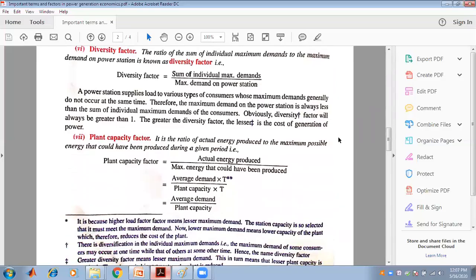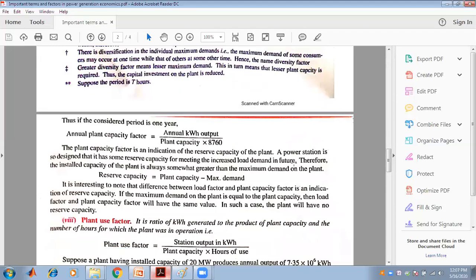The plant capacity factor is the ratio of actual energy produced to the maximum possible energy that could have been produced during a given period. It equals average demand multiplied by time t divided by plant capacity multiplied by time t, giving average demand divided by plant capacity. For a period of one year, the annual plant capacity factor is annual kWh output divided by plant capacity multiplied by 8,760. The plant capacity factor is an indication of the reserve capacity of the plant.